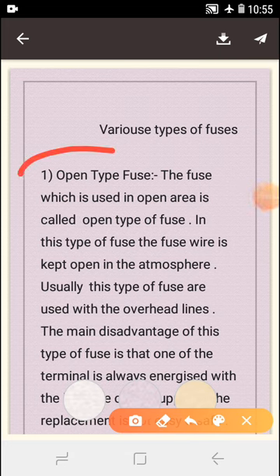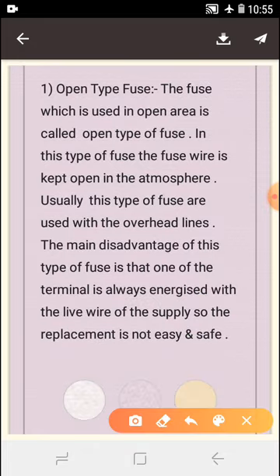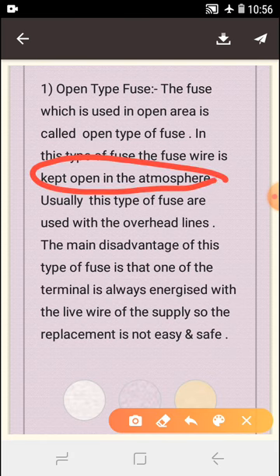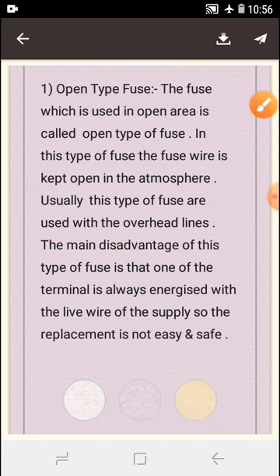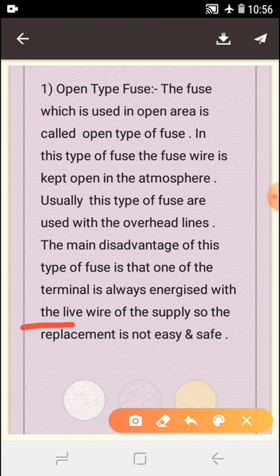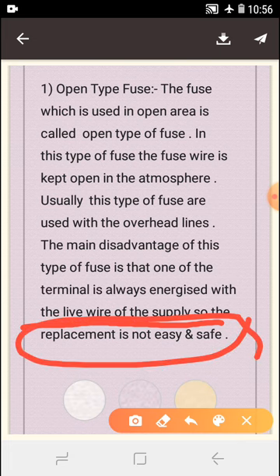The fuse which is used in an open area is called an open type fuse. In this type of fuse, the fuse wire is kept open in the atmosphere. Usually this type of fuse is used with overhead lines. The main disadvantage is that one terminal is always energized with the live wire of the supply, so replacement is not easy or safe.